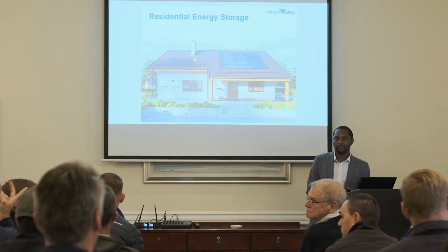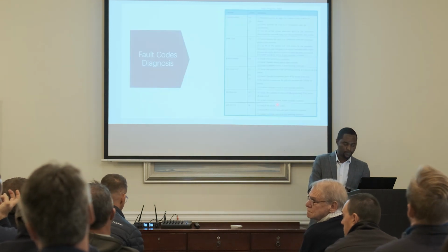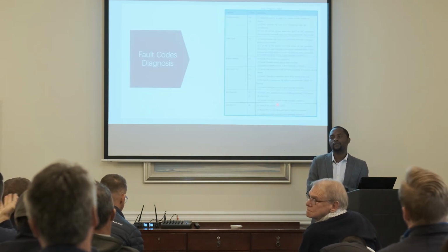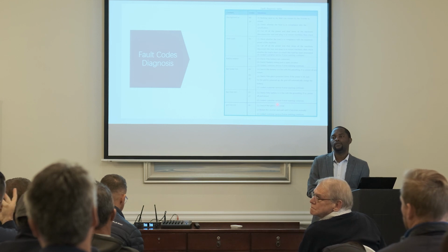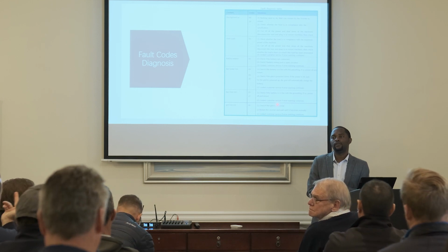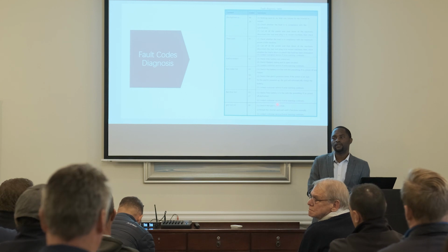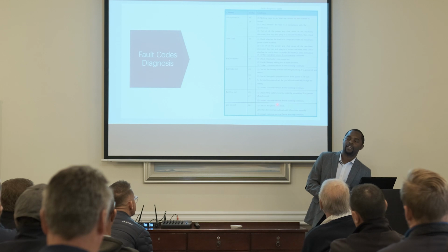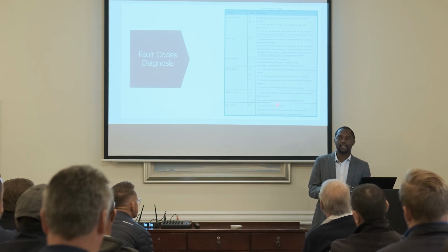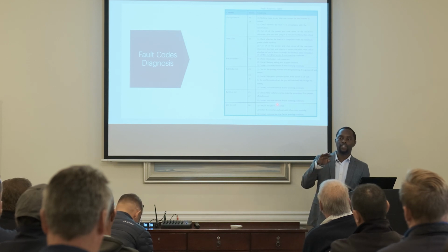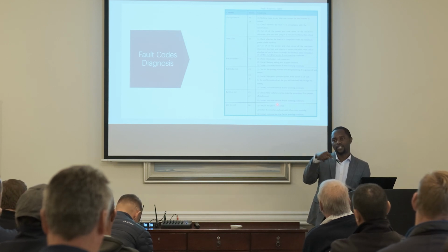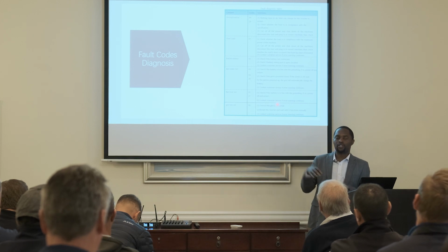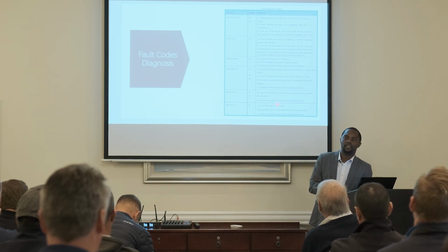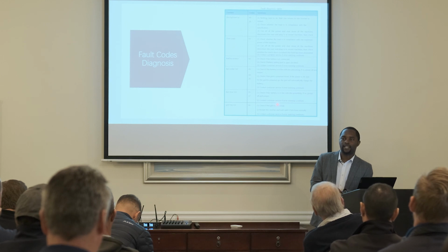Just on the output port, because you've got 2 ports now, if your staff accidentally, because obviously if you do a parallel system, you're going to bridge the outputs. If you bridge output 1 with output 2, for instance, will it give you an alarm? It will give you an alarm and you won't be able to operate with that. These are separate outputs. You can switch them on or off individually. So now it's not at the same point. You can't parallel across, and you get an alarm if you make that mistake.